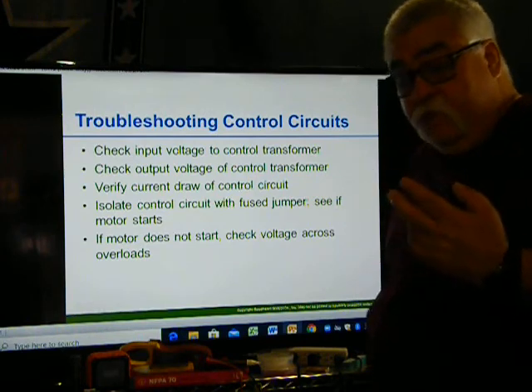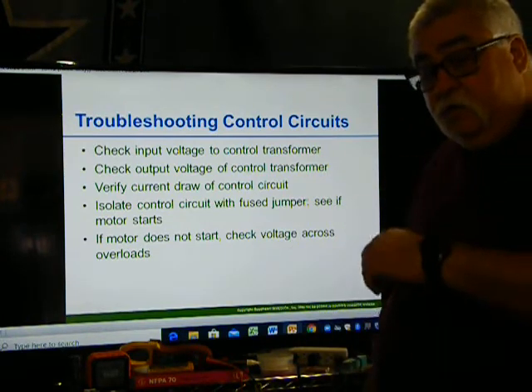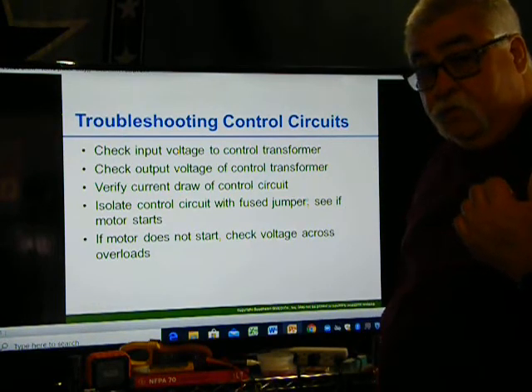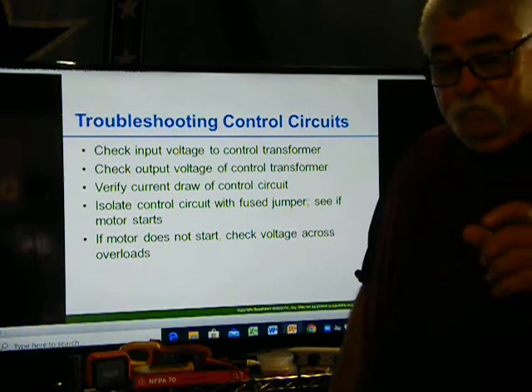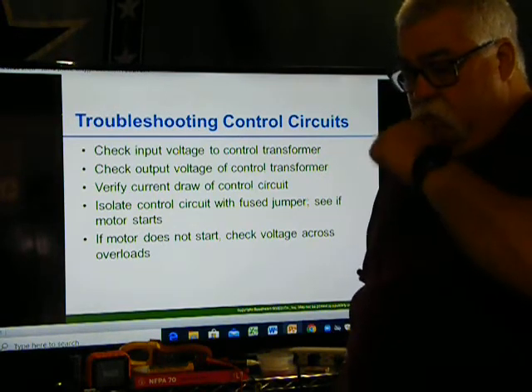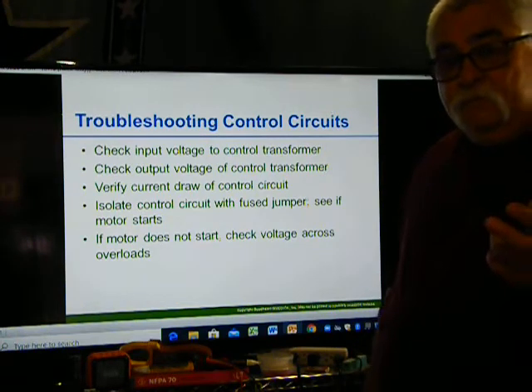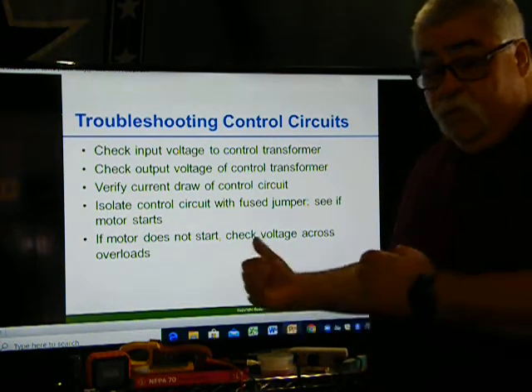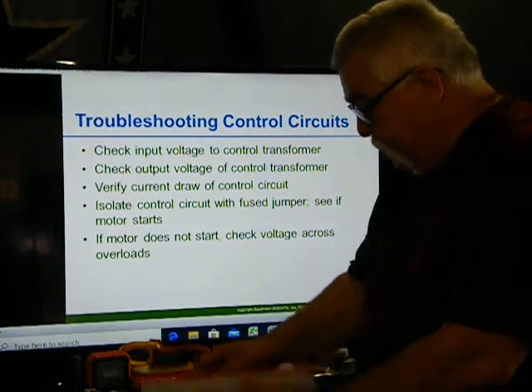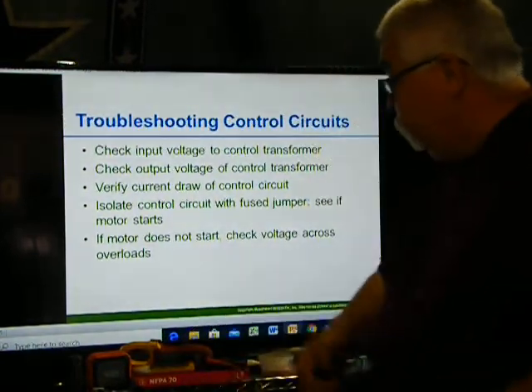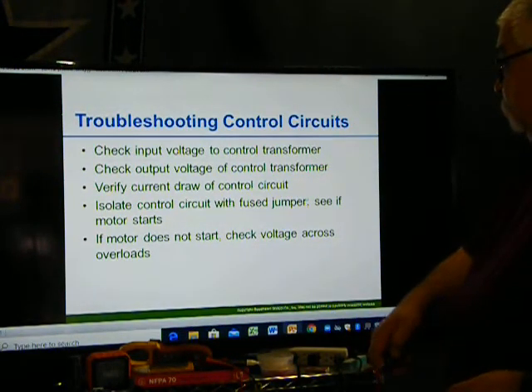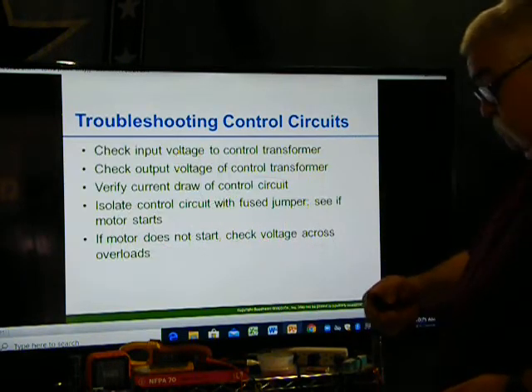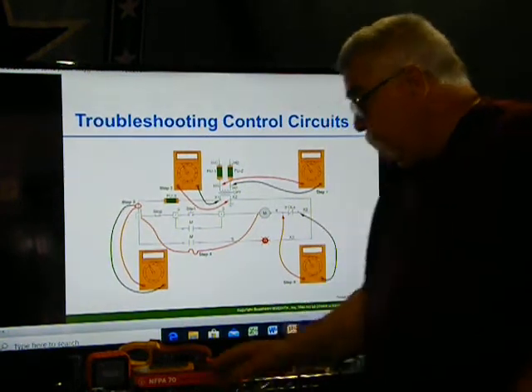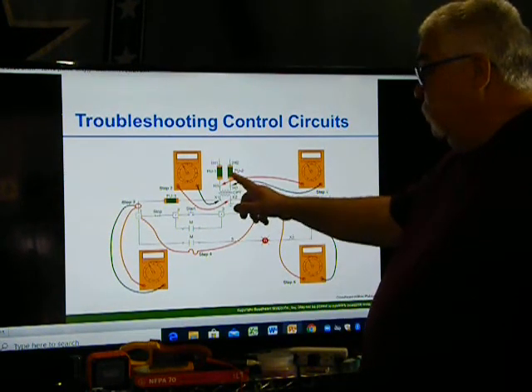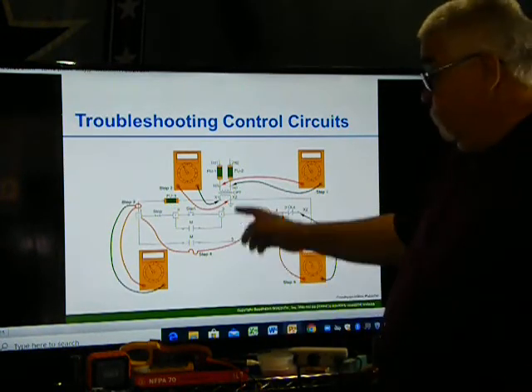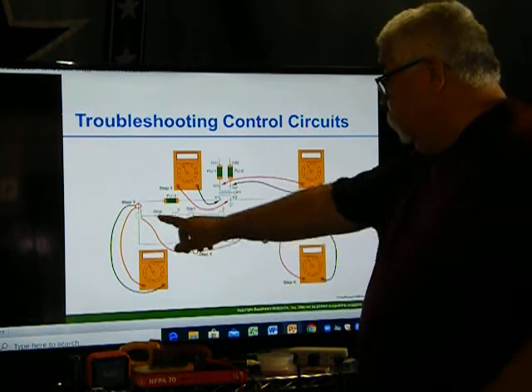Because sometimes you'll have a fuse on the transformer for your input, and you'll also have a fuse on your secondary side of the transformer going out for the control circuit. So that way it's protected on both sides. Why? If I got a 50 VA transformer, a 50 watt transformer, all it's doing is the controls, the stop starts. Let me see if I got a picture here for that. Okay, there it is. So there's a fuse on the primary side. There's a fuse on the secondary side. Why? This is a 50 watt transformer because all it's got to do is run the stop starts.